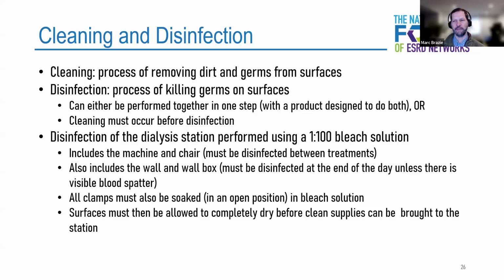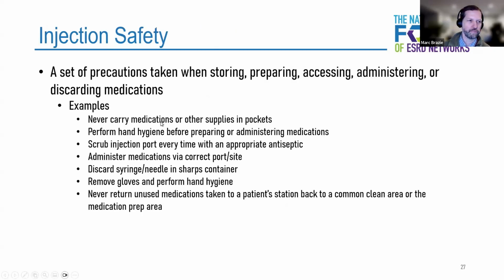The biggest mistake I see made with cleaning and disinfection in the dialysis unit is that people really want to do that changeover of that change of shifts as quickly as possible. And sometimes they will start to clean and disinfect the dialysis machine while the patient is still holding pressure over their access site. If the patient is still sitting in the chair, you cannot start cleaning and disinfecting their dialysis machine. You need to wait until that patient has left the unit, and then you can disinfect both the dialysis machine and the chair together. So you can't start while the patient's still there holding pressure on their access.